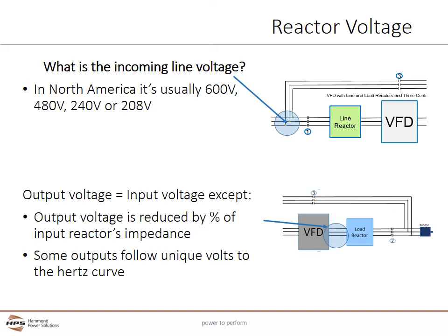Incoming voltage is typically easy to determine. In North America, it's usually 600, 480, 240, or 208 volts. Other voltages are available in the selection charts or the ePortal configuration systems. The output voltage equals the input voltage except the output voltage is reduced by the percent of the input reactor's impedance if an input reactor is used. Note that some VFD outputs follow a unique volts-per-hertz curve that may differ in both frequency and voltage from the input. Please consult HPS for these situations to properly size a load reactor.